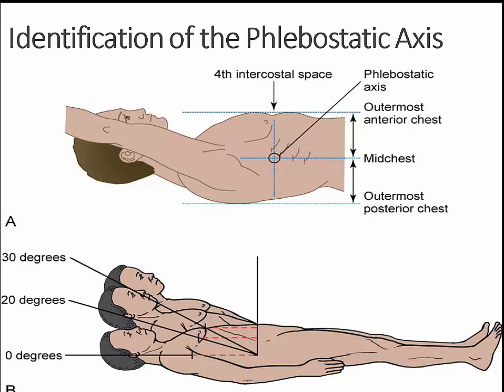The patient should be placed in a supine position whenever completing a hemodynamic assessment. The zero referencing point must be repositioned with changes in the backrest elevation to keep it at the phlebostatic level. To do this, open the reference stopcock to room air. This is off to the patient, and observe the monitor for a reading of 0. This allows the monitor to use the atmospheric pressure as a reference for 0.